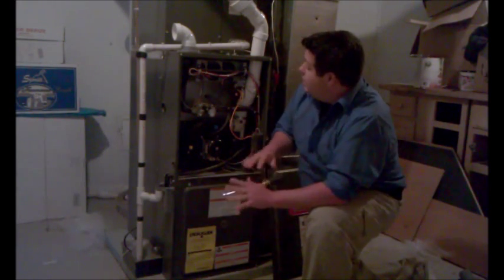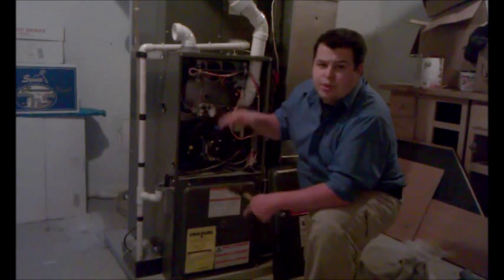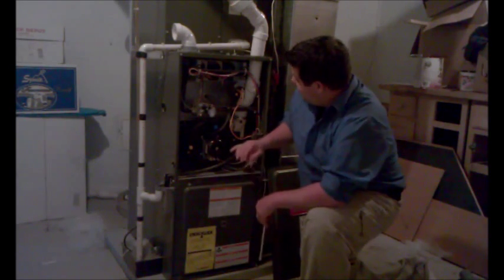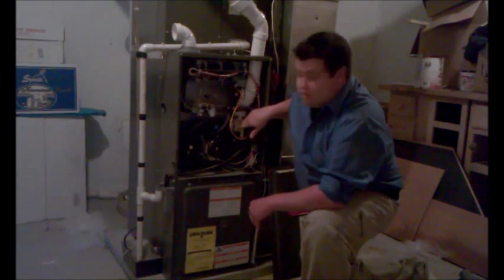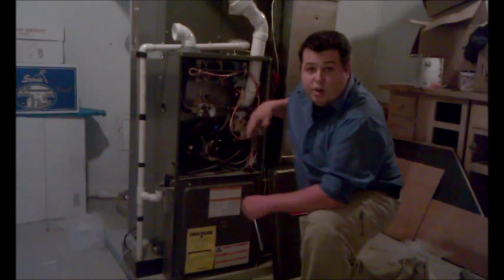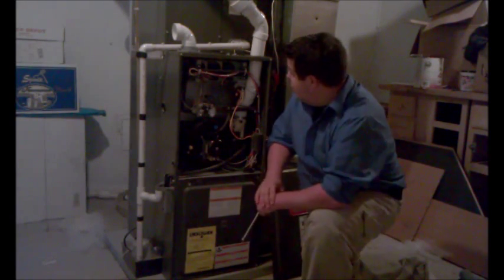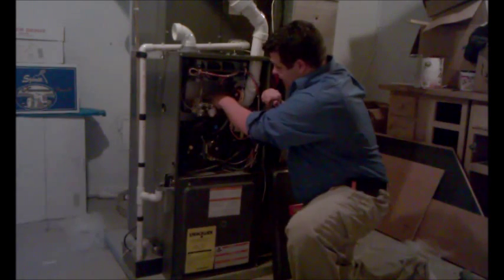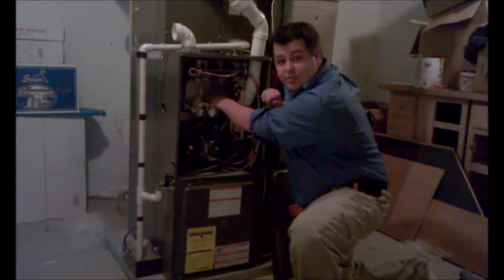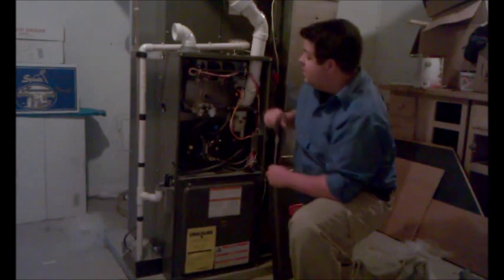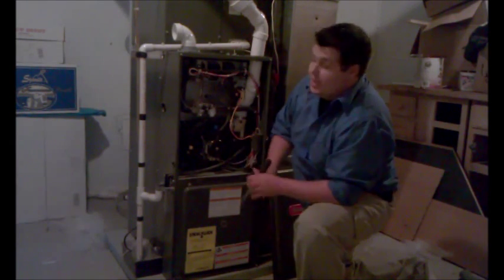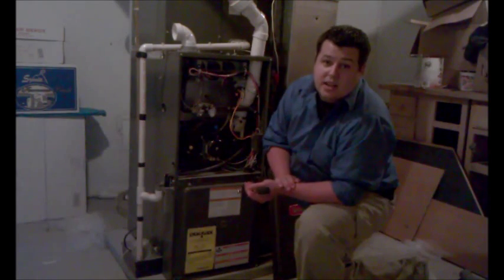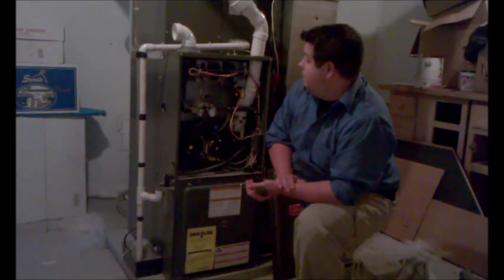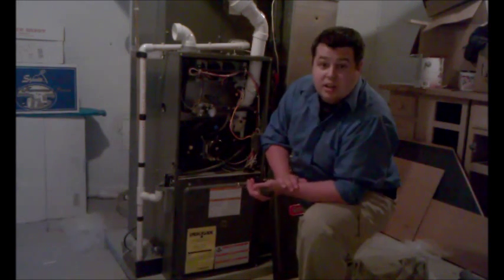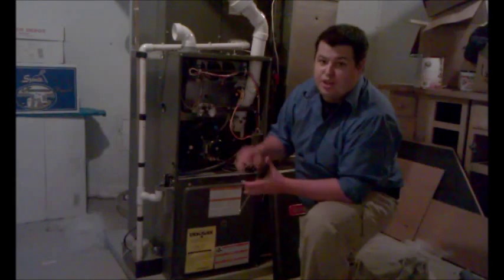So anyway, when we're looking at a furnace, what we're doing is we're going through and cleaning it out in the fall. We're checking to make sure the pipes are getting a good amount of air pressure through them, so it's taking all the carbon monoxide out of your house, so it's safe to run. We're also checking back here. There's a high limit switch that shuts the furnace off if the furnace overheats, and we're checking that. We're cleaning all the burners off, making sure that you're getting good flame and it's not going to be causing either the furnace not to light or causing any fire hazard or anything like that.